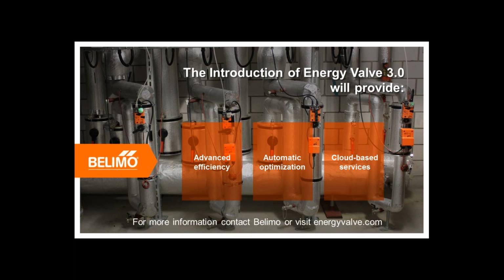Next question. These valves can be used in water-cooled condenser chillers to control the condenser pressure? They can control the flow, yes, and by being pressure independent, we can keep the pressure at a certain level, but we don't have pressure control for the valves.